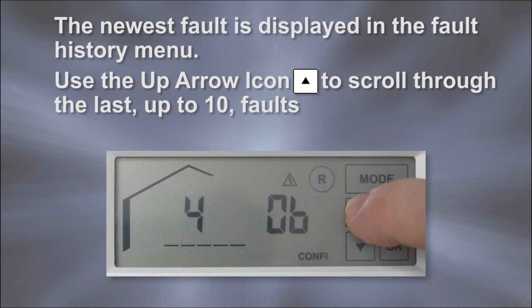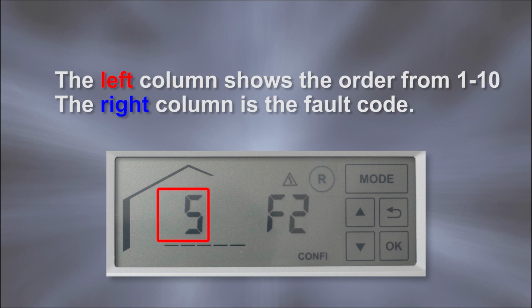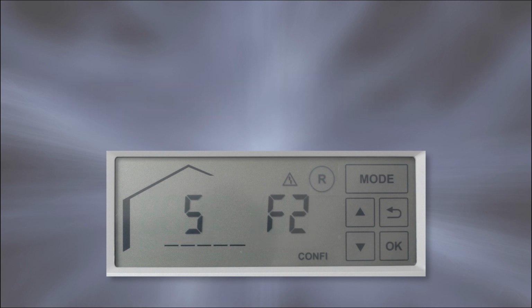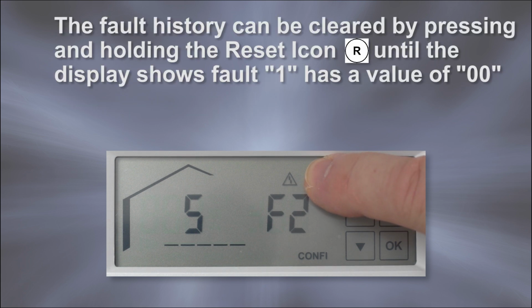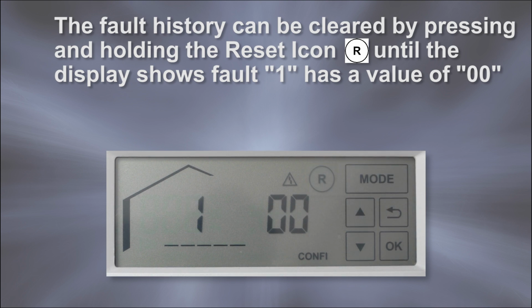If there are less than 10 faults, the display will stop at the oldest fault. The left column shows the order from 1 to 10, and the right column displays the fault code. The fault history can be cleared by pressing and holding the reset icon until the display shows fault 1 has a value of 0, 0.